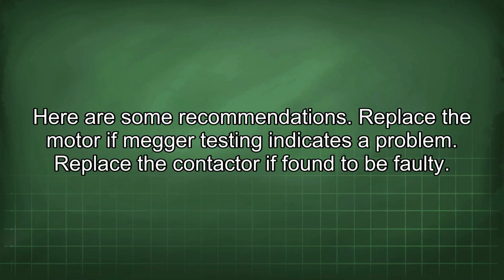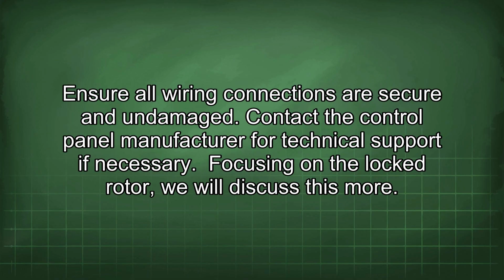Here are some recommendations. Replace the motor if megger testing indicates a problem. Replace the contactor if found to be faulty. Ensure all wiring connections are secure and undamaged. Contact the control panel manufacturer for technical support if necessary. Focusing on the locked rotor, we will discuss this more.